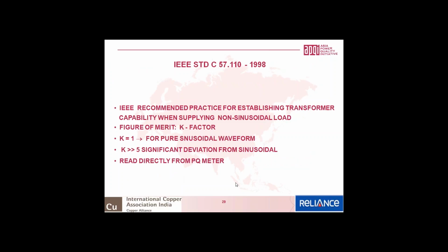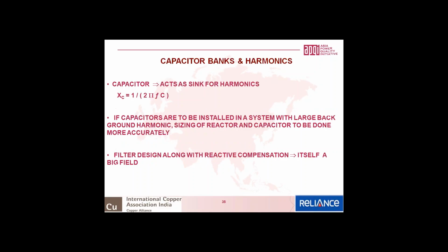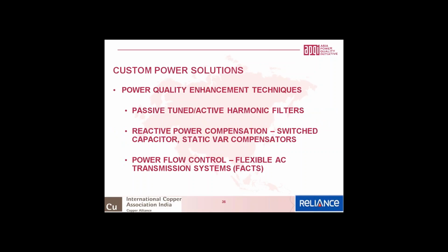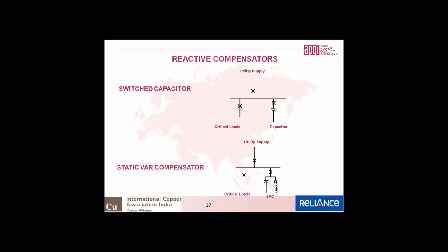In systems with large background harmonics, the sizing of reactors and capacitors has to be done more accurately. Filter design itself, as Dr. Venkatesh has pointed out, is a very big topic by itself. Custom power solutions, again Dr. Venkatesh has talked about the passive and active filters. Then there is reactive power compensation: the conventional switched capacitors, static VAR compensators, and, in very high voltage networks, the flexible AC transmission devices, what we call FACTS devices.